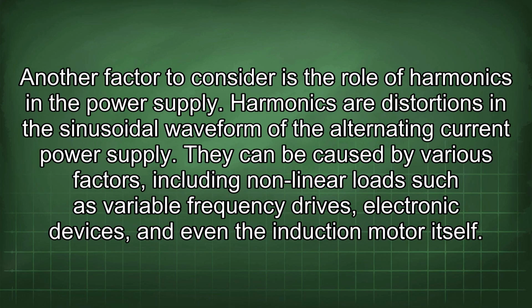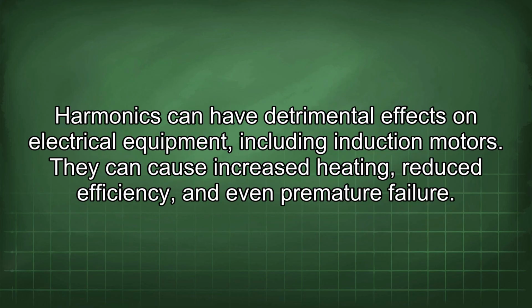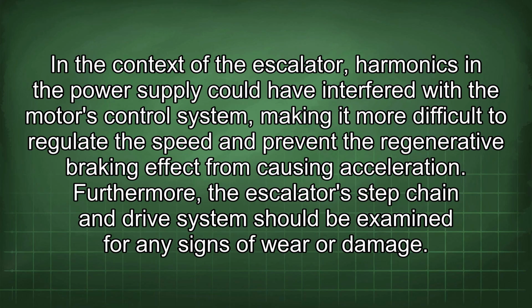Another factor to consider is the role of harmonics in the power supply. Harmonics are distortions in the sinusoidal waveform of the alternating current power supply. They can be caused by various factors, including nonlinear loads such as variable frequency drives, electronic devices, and even the induction motor itself. Harmonics can have detrimental effects on electrical equipment, including induction motors. They can cause increased heating, reduced efficiency, and even premature failure. In the context of the escalator, harmonics in the power supply could have interfered with the motor's control system, making it more difficult to regulate the speed and prevent the regenerative braking effect from causing acceleration.